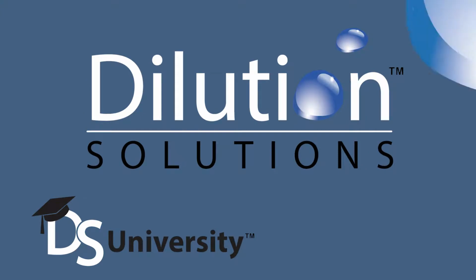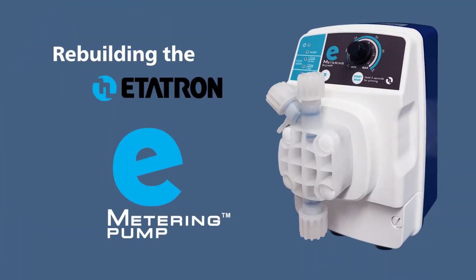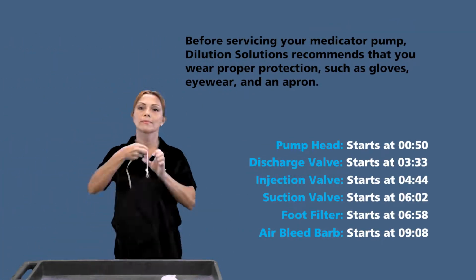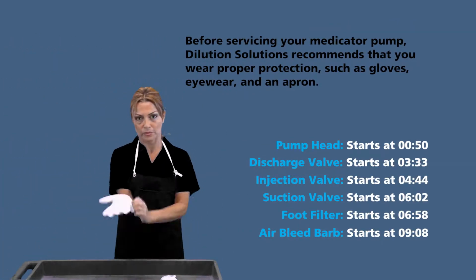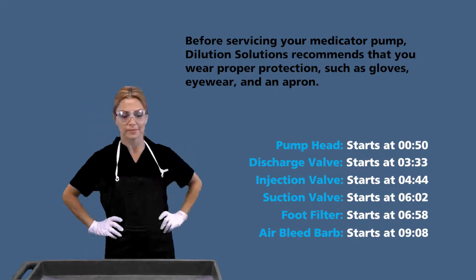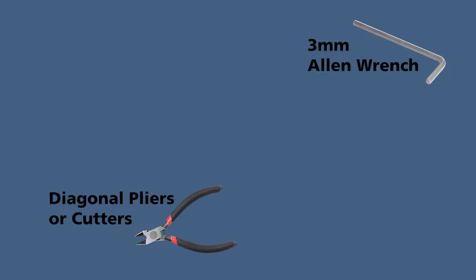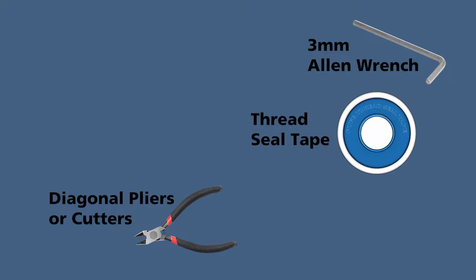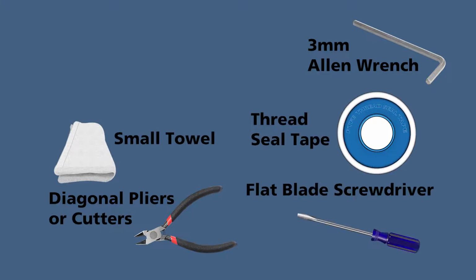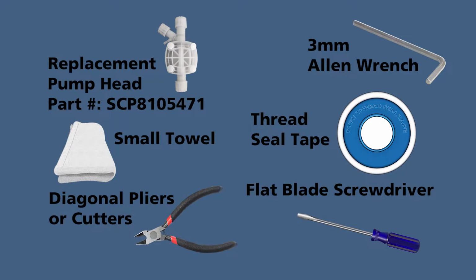DS University. In this video, we are going to cover the steps on how to rebuild the eMP metering pump. The rebuild can be performed with the pump still mounted on the wall. It's best to perform the rebuild in a clean area, so make sure to cover your chemical bucket so you don't lose any parts. To start, you will need a 3mm Allen wrench, diagonal pliers or cutters, thread seal tape, a small towel, a flat blade screwdriver, the replacement pump head, and the tubing kit.